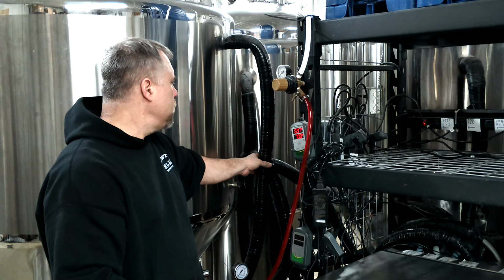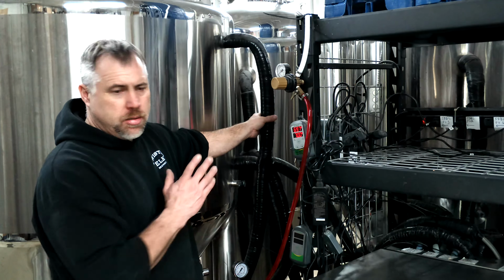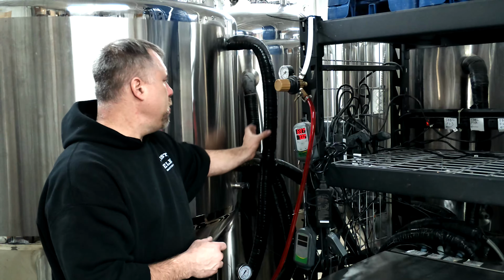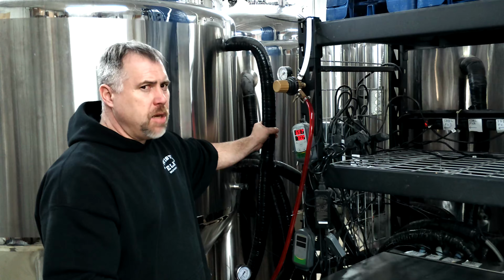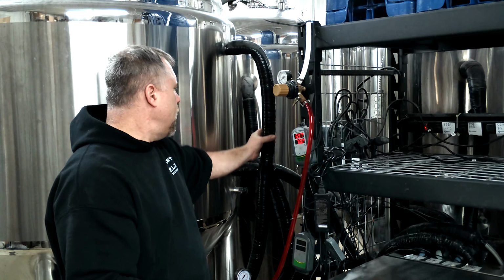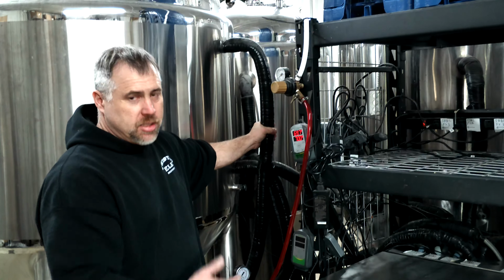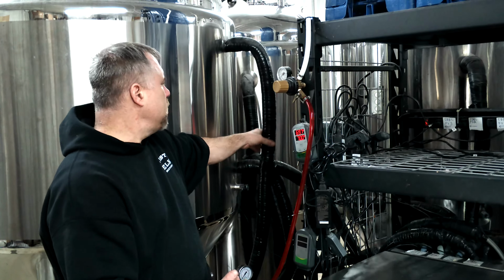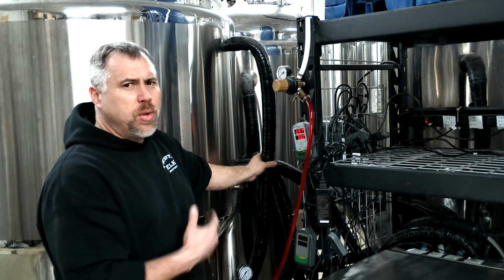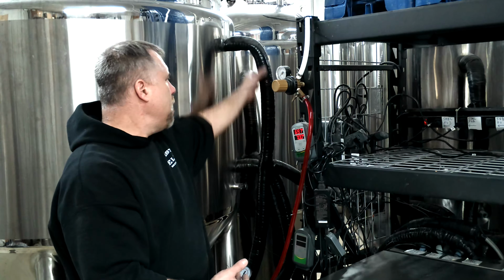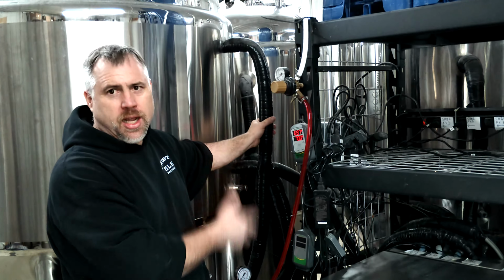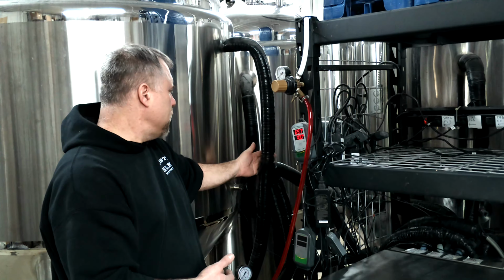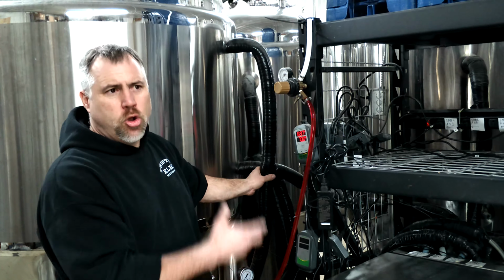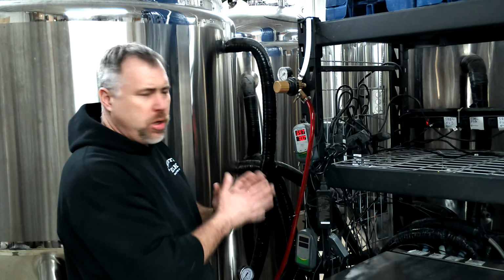After we got everything plumbed in, I went over it with 2 layers of pipe insulation. I used 1/2-inch foam insulation around the tubing first. Then we found the biggest one we got, I think it might have been 1 inch or 1.5 inches, and we wrapped that on top of that, so 2 layers. Then we took that and wrapped it with electrical tape. We did that pretty much just to seal it and make it so you can clean it, so you can actually wipe down the electrical tape. It was a lot easier than the foam, which is kind of like a porous surface.